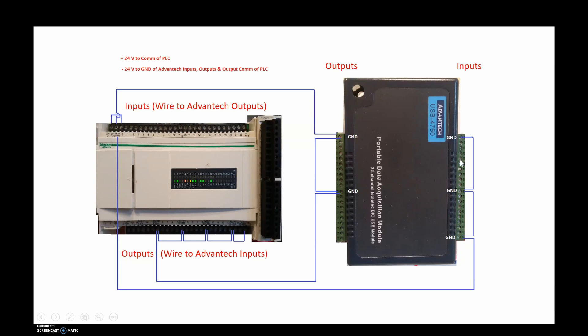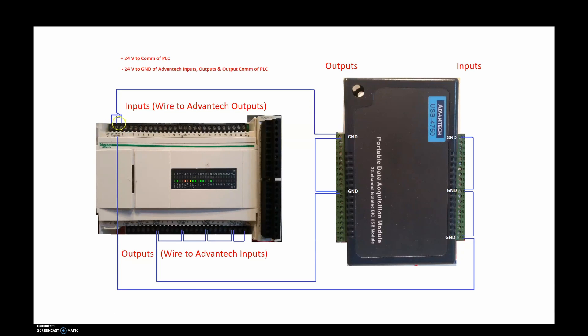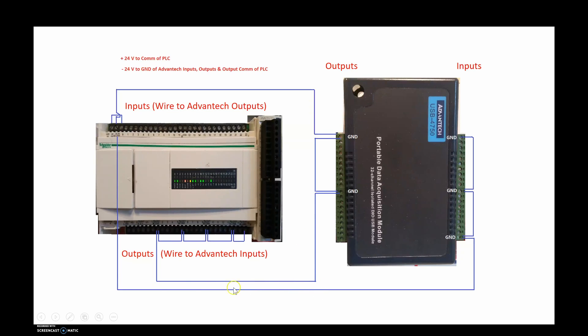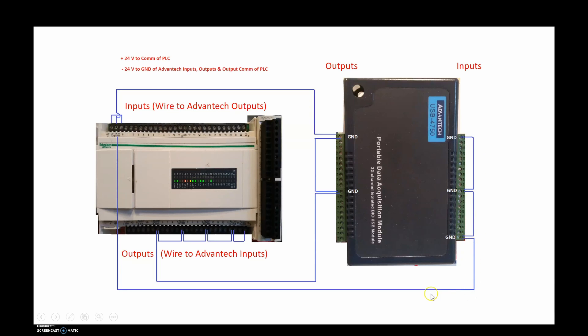Now with the wiring of the positive and negative 24 volts DC, I have the positive 24 volts going to the common of my PLC on my inputs. And the negative is going over here and tying into all of the grounds on the outputs of the Advantech. They're also tying into the commons of my PLC on the outputs and on the input terminals of the Advantech. We're also going to take all the grounds and jumper them together and bring them to the negative of our 24 volt power supply on the PLC.